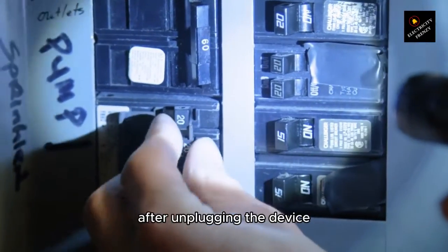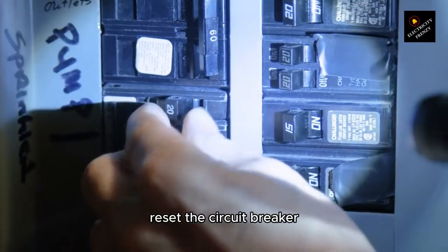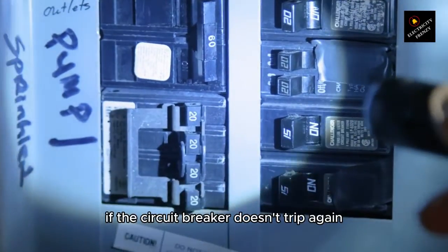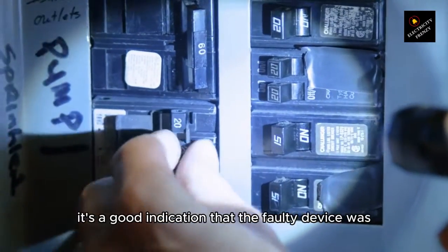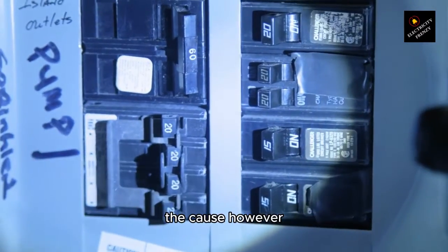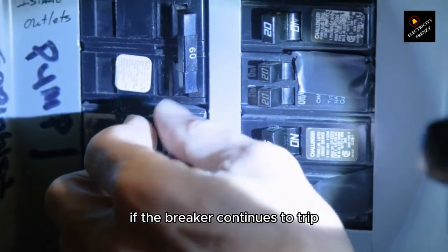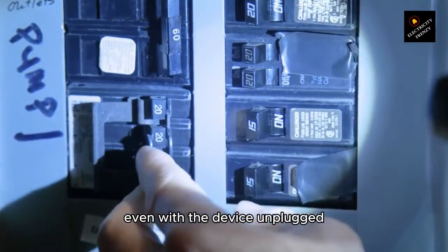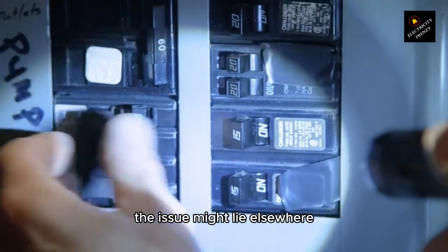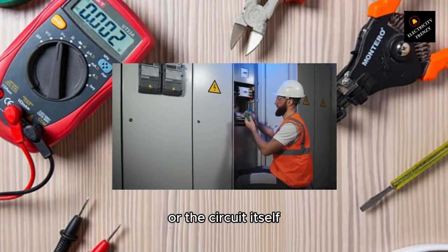Test the circuit. After unplugging the device, reset the circuit breaker if it has tripped. If the circuit breaker doesn't trip again, it's a good indication that the faulty device was the cause. However, if the breaker continues to trip even with the device unplugged, the issue might lie elsewhere, such as with the wiring or the circuit itself.